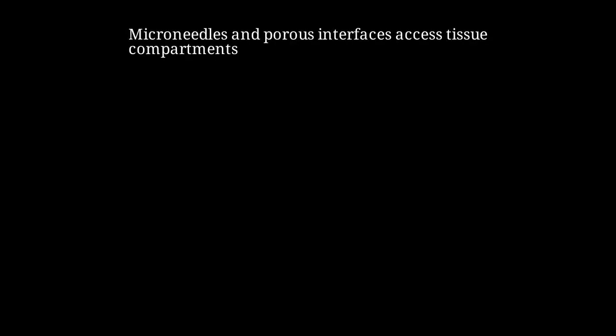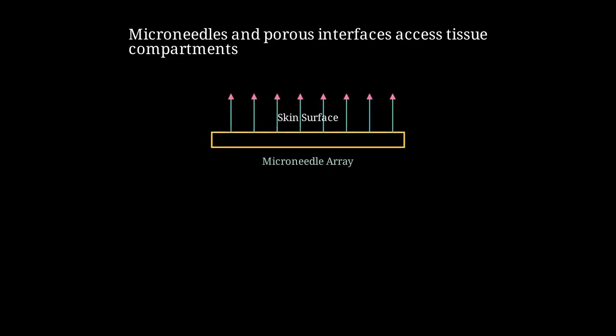Channel geometry, wettability, and surface energy are precisely engineered to route fluids without leakage or backflow through Laplace pressure gradients. Channel height directly controls hydraulic resistance, with narrower channels providing higher resistance and better flow control through precise dimensional engineering. Microneedle arrays and porous membranes lower transport barriers, allowing controlled extraction of interstitial fluid from beneath the skin surface. Hollow microneedles penetrate the stratum corneum to draw interstitial fluid into microchannels at controlled rates for continuous glucose or drug monitoring.